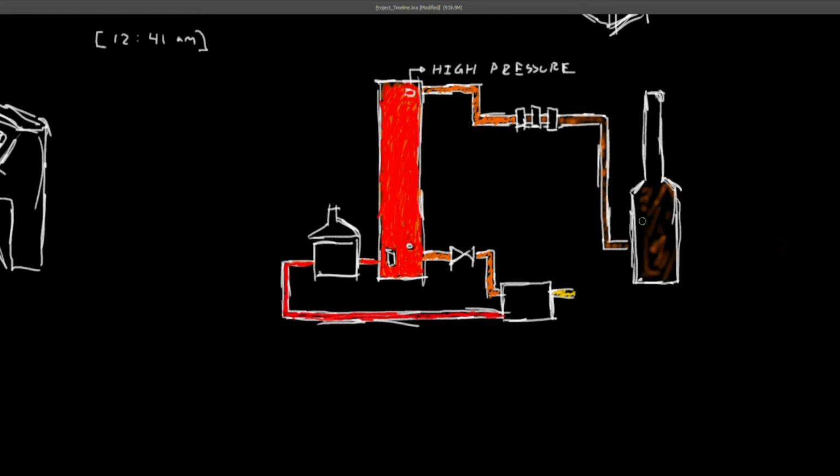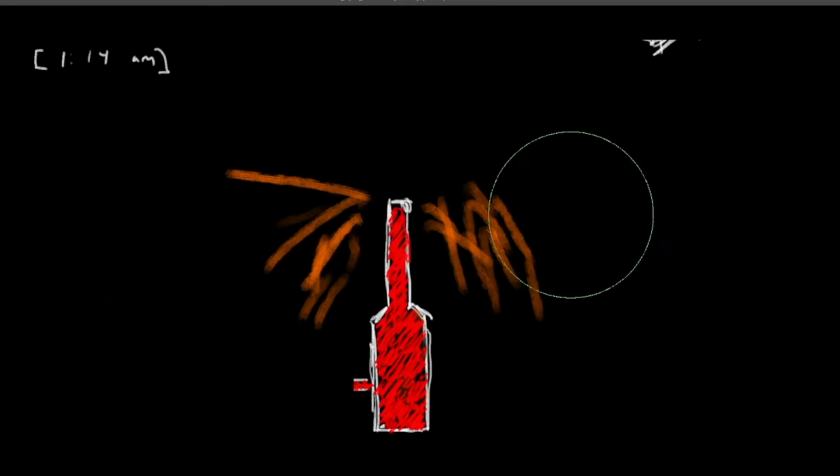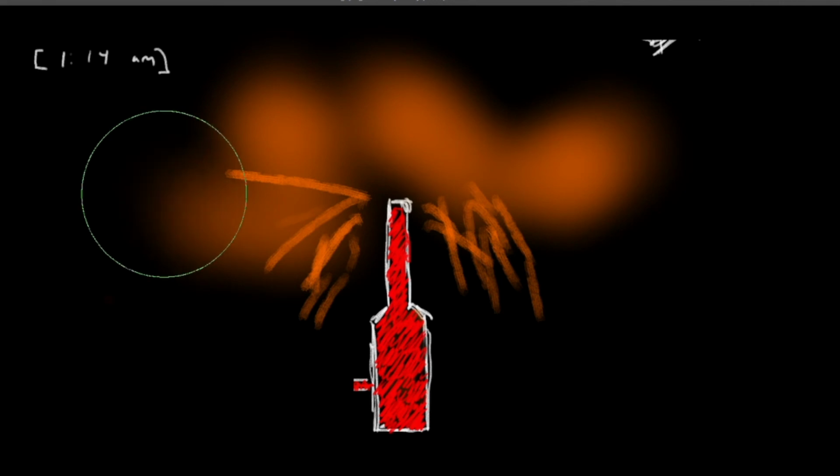Another high-level alarm in the blowdown drum failed to go off as the hot liquid level continued to rise to the top of the blowdown drum, causing a mixture of flammable vapor and liquid to erupt from the top of the blowdown drum. This formed a huge vapor cloud that expanded in 90 seconds, enough to engulf the ISOM unit and the nearby trailers that the maintenance workers occupied. 1:20 a.m., an idling truck engine nearby ignited the vapor cloud, causing a huge explosion.